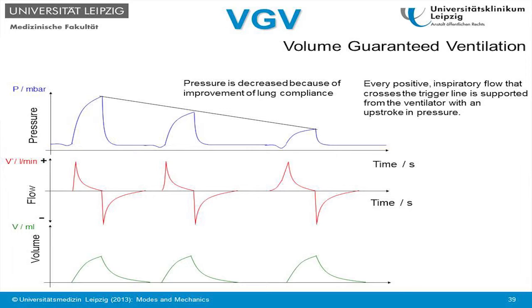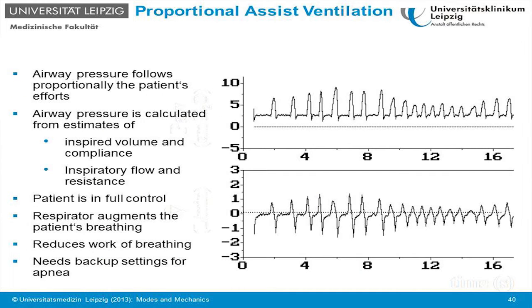which has been shown in studies to end up with a lower average airway pressure than when we have not volume guarantee ventilation, but pressure controlled ventilation with the preset pressure, because the machine continuously tries to wean the patient whenever this is possible. So this seems to be a very gentle and also flexible mode of ventilation. However, you obviously need a flow sensor to do that, and the flow sensor, as I told you, may require higher ventilator settings from the beginning.